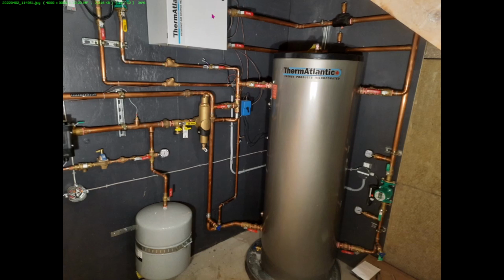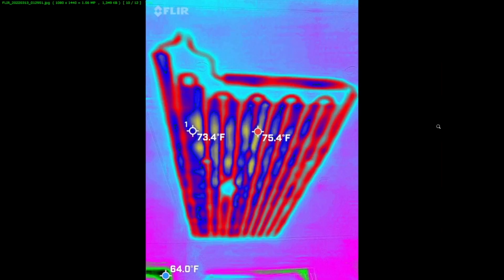Just one thing before I go there. I was doing some testing, and I actually am embarrassed to say that I had miswired. There was something lost in translation between the time I roughed in my ceiling panels and put in the manifolds and the zone actuators, and the time that I put in the instrumentation. I did not match those two processes up, and so I ended up miswiring a lot of my actuators. So I let the system cool down, and then I would open one actuator at a time and use my FLIR camera to identify what zone was open.